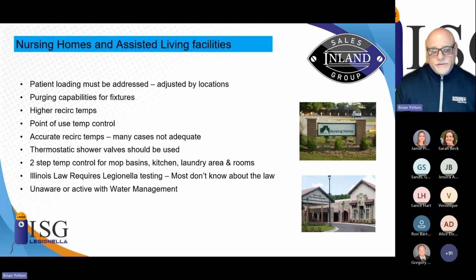When we think about nursing homes, patient loading needs to be addressed. If you're not full, don't put patients at the end of the run, get them closer to the mechanical room. Maybe use purging facilities, higher recirculation temperatures, make sure temperatures are where they need to be, and use thermostatic controls at the point of use or at the shower. The state of Illinois requires Legionella testing for every nursing home, but they don't tell you what to do with it.